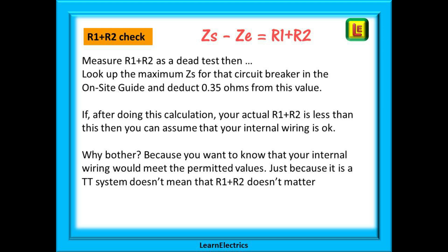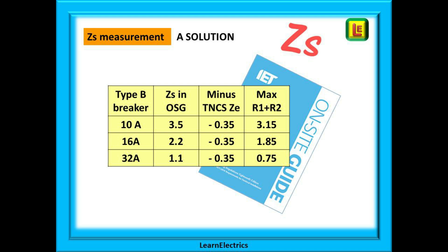Why 0.35 ohms? That's because that number is the maximum ZE for a TN-C-S system, and that's the only thing we have right now as a reference for a normal ZE. If your actual measured R1 plus R2 is less than this calculated value (ZS minus 0.35), then you can assume that your internal wiring is okay. We bother with this because you want to know that your internal wiring would meet the permitted values — just because it is a TT system doesn't mean R1 plus R2 doesn't matter. It matters very much for short circuit protection, for overload and for voltage drop. So don't ignore it — get it right, be professional.